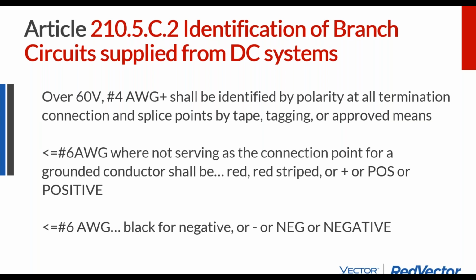And in fact, the National Electrical Code says those circuit conductors up on your solar array, up on your rooftop, need to be in colored cable, number 6, red for positive, black for negative. And that's not in Section 690, that's in Article 210.